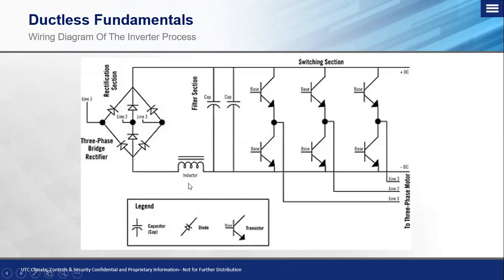Okay, so this is filtering the DC voltage, and then next we run it through a capacitor bus. Now, capacitors by nature store and release charge. This is in an effort so that when that sine wave reaches its peak, these capacitors are going to absorb that charge. And when that sine wave reaches the very pit or the bottom of its wave, they're going to discharge. Now that works in an effort to keep that sine wave as smooth and clean as possible. Essentially, we're trying to keep it perfectly straight. While it'll never achieve that, it is going to work in unison with the inductor or the reactor to try to keep a smooth, clean, consistent sine wave. In this case, we're looking at a DC sine wave or power that's feeding into our next part that we're going to look at right now.